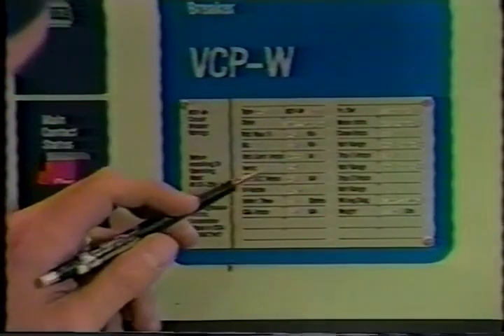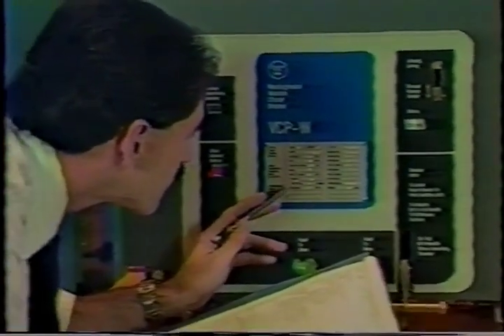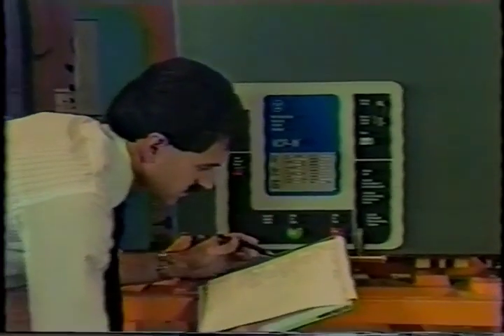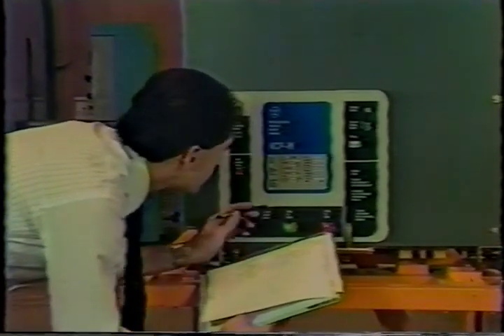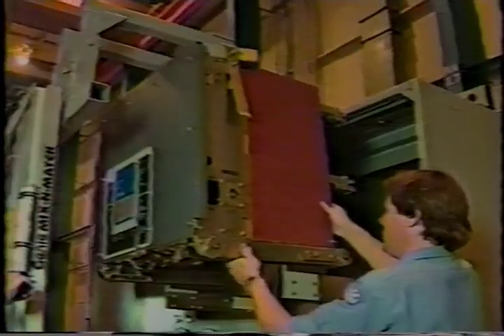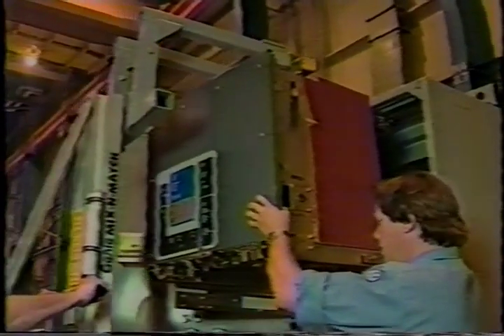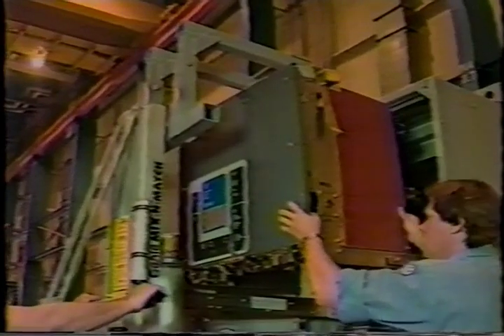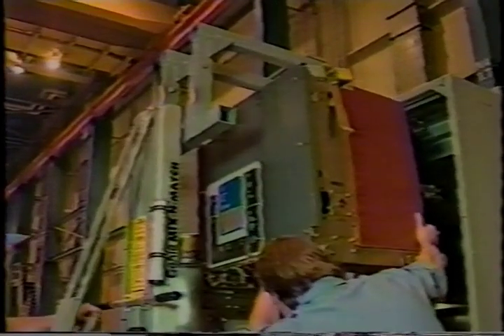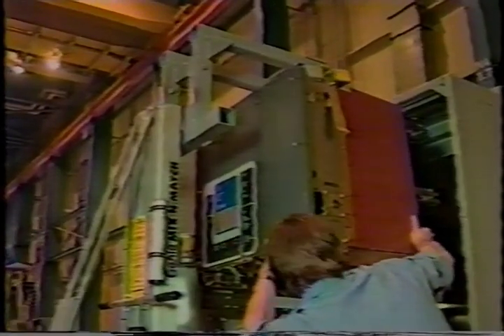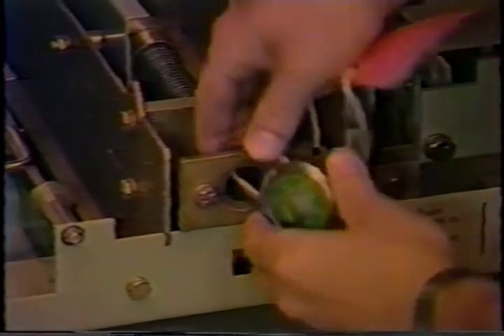Compare the breaker nameplate information with the switchgear drawings for compatibility. Breaker and compartment code plates match power ratings. They do not match control voltages. After going through the preceding steps, the breaker is ready to be operated electrically. It is preferred that this check be made with the breaker in the test position in the breaker compartment. While checks are performed in the breaker compartment, care must be exercised to make certain that the primary circuit is not energized.